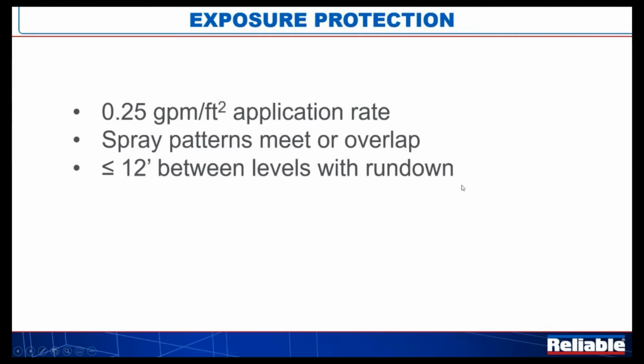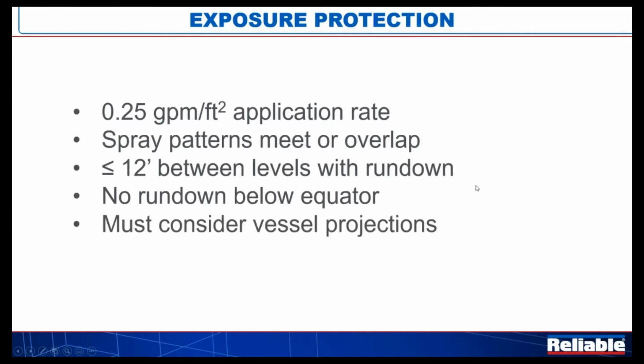Above the equator of the tank, no more than 12 feet on center. And again, down to the equator, you have what we call rundown, so you get some help with that. Once you're below the equator, we don't consider rundown, even though it's going to happen to a certain degree. We're not allowed to consider it anymore. That's why you saw in that spherical tank, the rings at the equator got closer together down at the bottom. It's a pretty easy concept to understand.